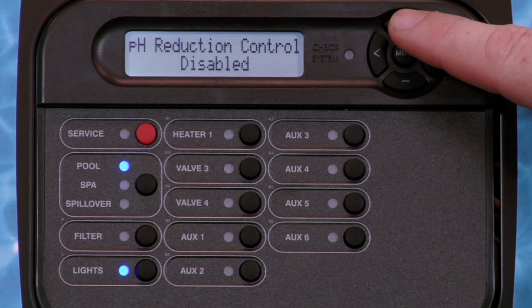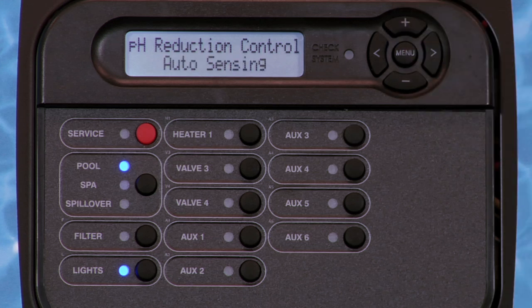Pressing the plus key will change the bottom line of the display to read auto-sensing. This function is used to allow Sense and Dispense to monitor pH levels in the water and to turn on reduction control as needed to adjust the pH to meet the selected parameters.